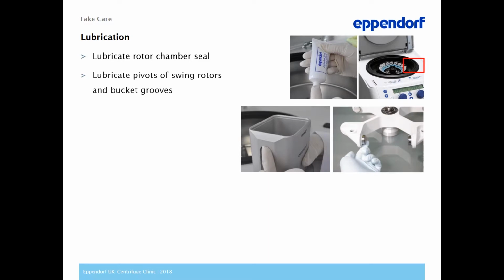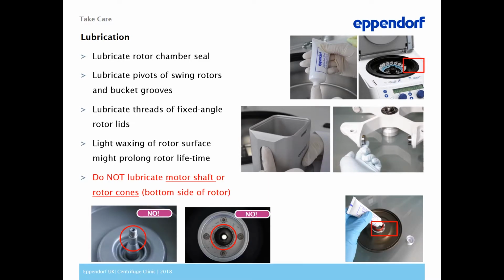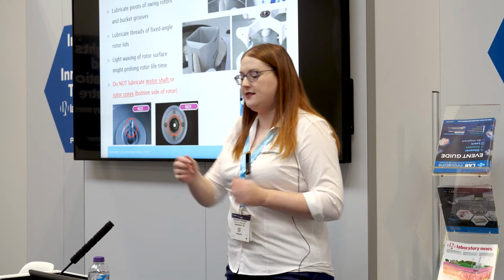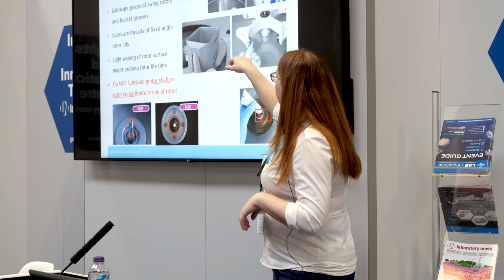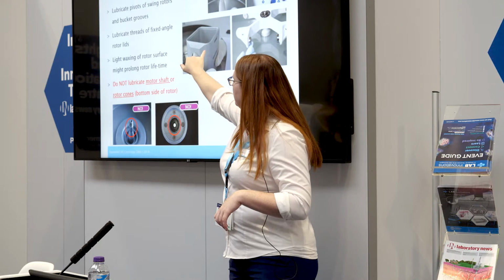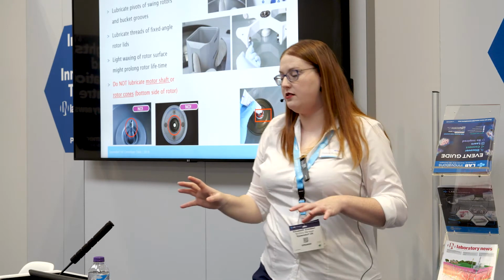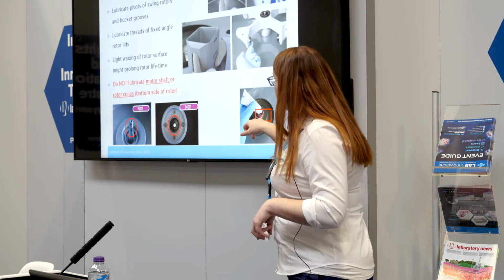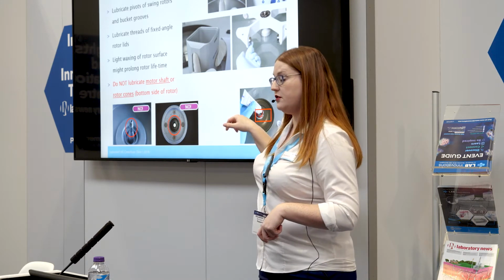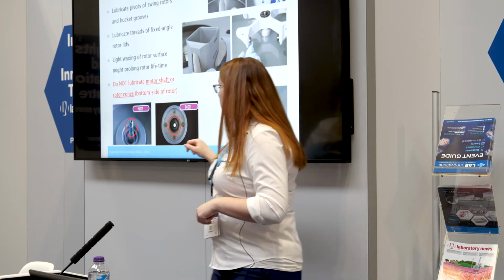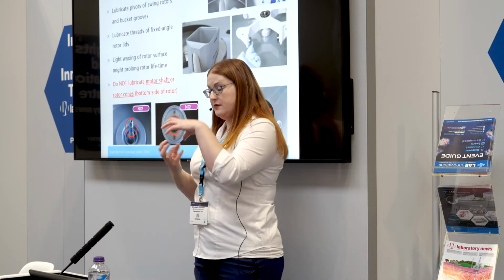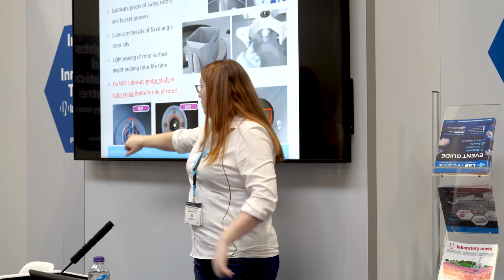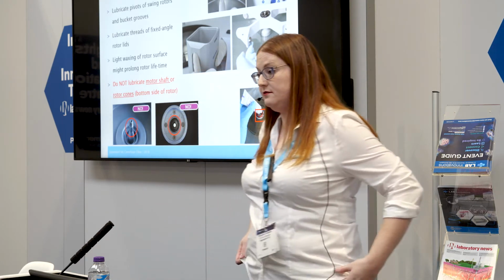So when it comes to lubrication, there are specific spots that you should and should not lubricate. Around the rotor chamber, so you get a nice tight seal between the chamber and the lid. Good start. On the swing out rotors, the connector points between the bucket and the rotor, always worth putting a bit of grease on them. And it's also a good idea to put some on the inside of the threads of your rotor lids for fixed angles. Don't do it on the motor cone, which is the bit on the underside of your rotor, or the motor shaft, because then they can't make proper contact, so you're not going to get proper spinning.